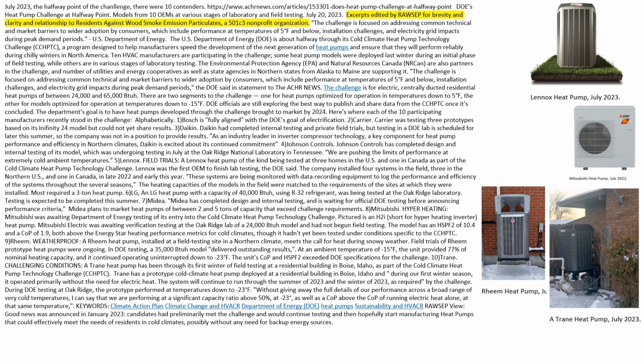The system will continue to run through the summer of 2023 and the winter of 2023, as required by the challenge. During DOE testing at Oak Ridge, the prototype performed at temperatures down to minus 23 degrees Fahrenheit. Without giving away the full details of our performance across a broad range of very cold temperatures, I can say that we are performing at a significant capacity ratio above 50% at minus 23 degrees, as well as a COP above the COP of running electric heat alone at that same temperature.